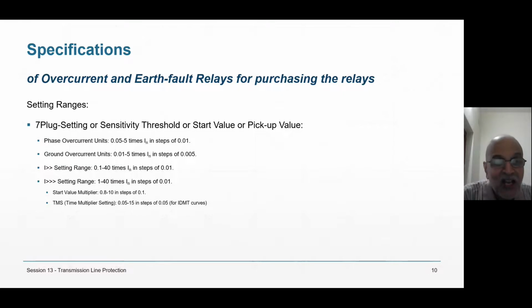So your high set setting has to be more than 10 times. If 100 ampere is your transformer primary current and a 100 by 1 CT is there, then 10 times means 10 ampere on the secondary side. So your high set setting has to be more than 10. But then for a 5 times fault, 500 ampere, it will not operate. It will operate only after time delay, and within that time the transformer will just blast.